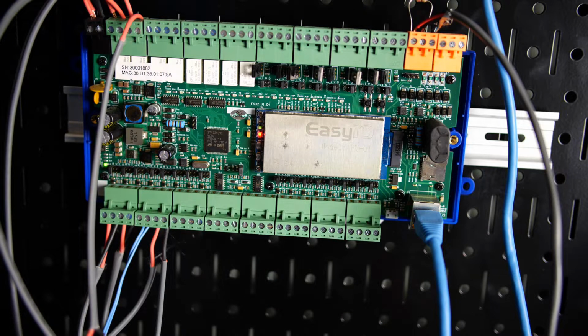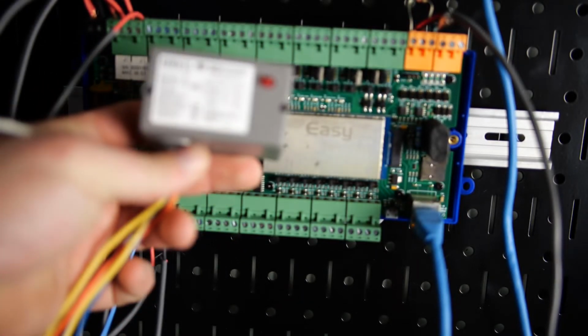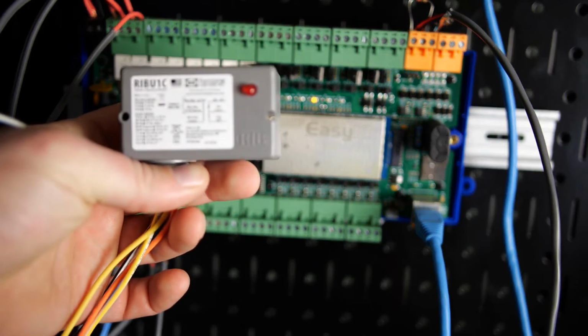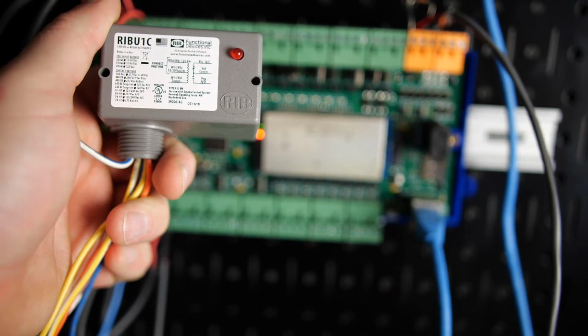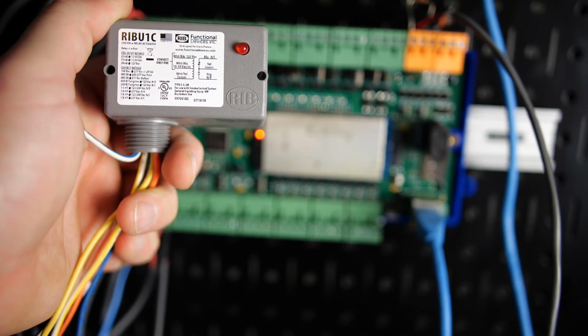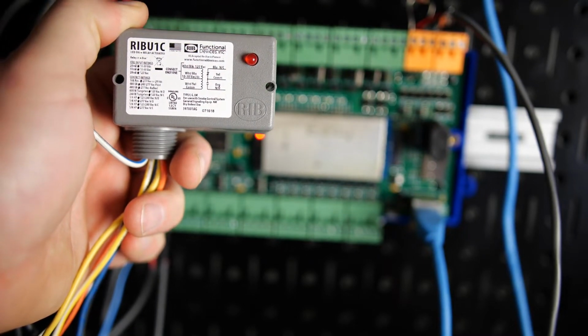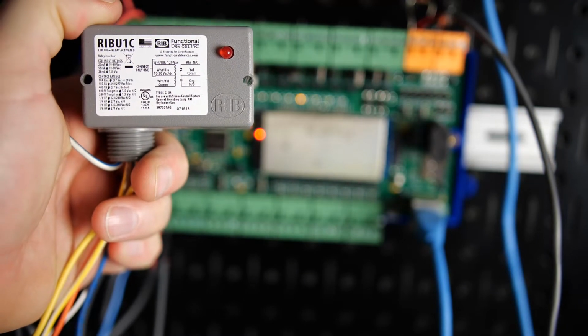The downside of using relays internally is that if we are using internal relays and we get some form of voltage surge, then we are literally screwed. We're going to let the smoke out of our controller, as it's called, which basically means we're going to melt the motherboard, or at least blow the output. And that's not good. So that's why we typically recommend these things right here, which are known as relay in a box, right? The relay in a box, the RIB right here, is an actual relay in a box, and you can kind of see now that the autofocus is catching up that it has what's called a coil, and it has contacts. The coil is what gets energized by some voltage and then causes the contacts to change state.